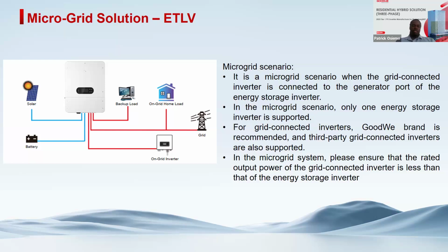This allows you to utilize the existing PV system along with the new technology that GoodWe has brought in, and then your system will be expanded in terms of capacity, in terms of usage, in terms of functionality as well. So both inverters can then operate off-grid and support your backup loads as well as charging your battery. So you can fully go off-grid in case the grid fails. Now that is the microgrid solution that the ETLV can achieve.